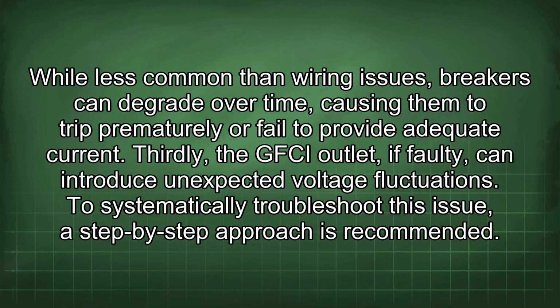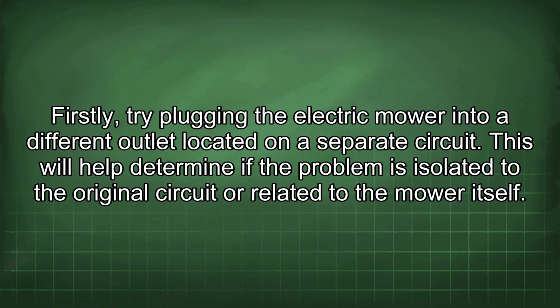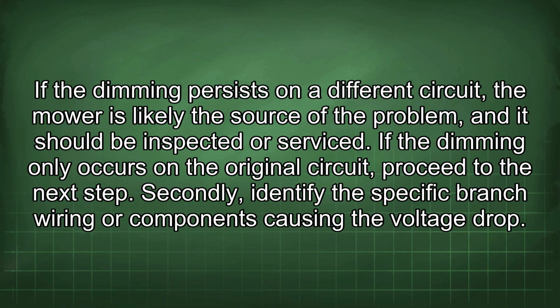To systematically troubleshoot this issue, a step-by-step approach is recommended. Firstly, try plugging the electric mower into a different outlet located on a separate circuit. This will help determine if the problem is isolated to the original circuit or related to the mower itself. If the dimming persists on a different circuit, the mower is likely the source of the problem, and it should be inspected or serviced. If the dimming only occurs in the original circuit, proceed to the next step.